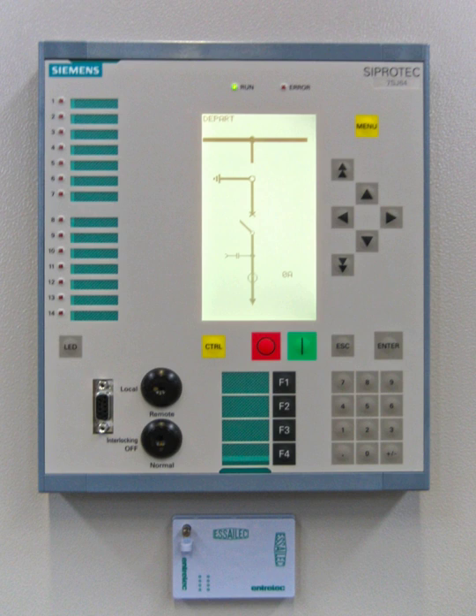Topic: Types of protection. Topic: High voltage transmission network. Protection on the transmission and distribution system serves two functions: protection of plant and protection of the public, including employees. At a basic level, protection disconnects equipment which experiences an overload or a short to earth. Some items in substations, such as transformers, might require additional protection based on temperature or gas pressure, among others.